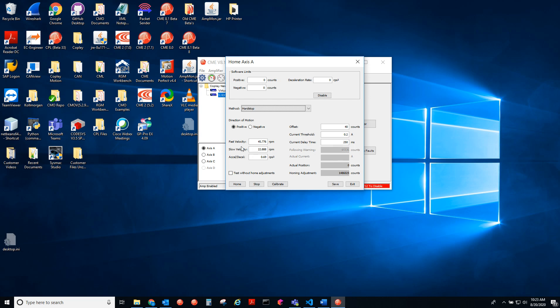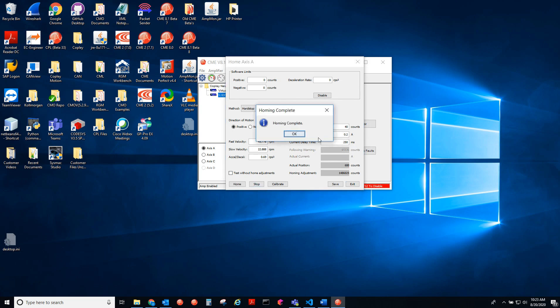Here we have other homing parameters as well as some feedback information here. So if I hit the home button, we're jogging in the positive direction. And once the current exceeds 0.2, we've hit the hard stop.